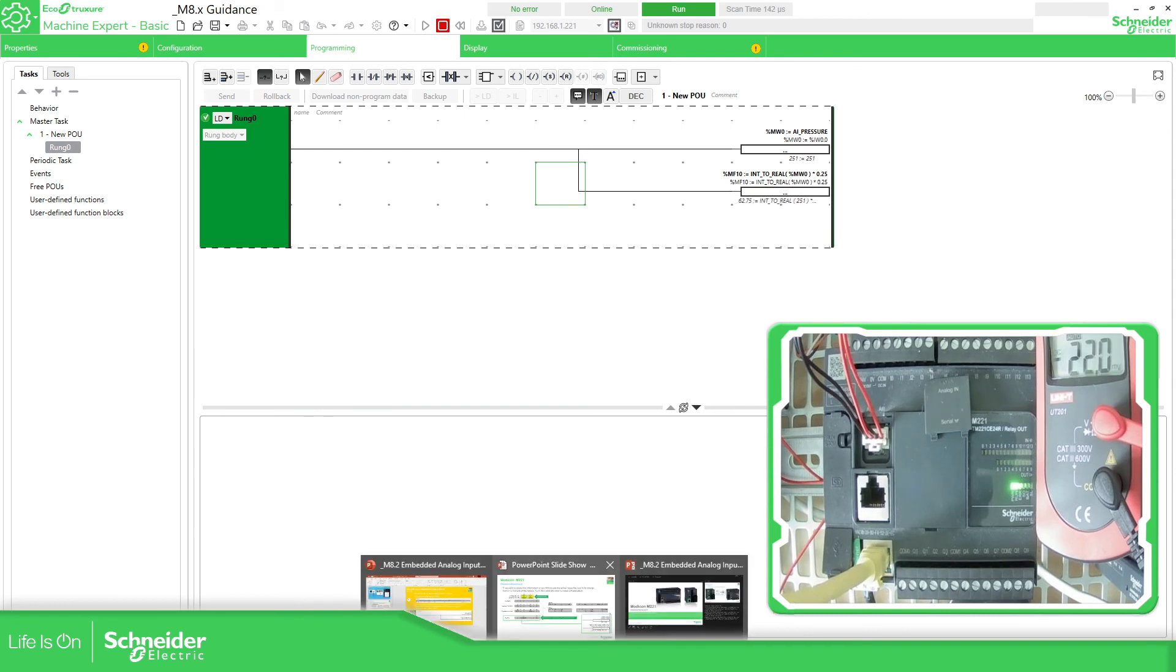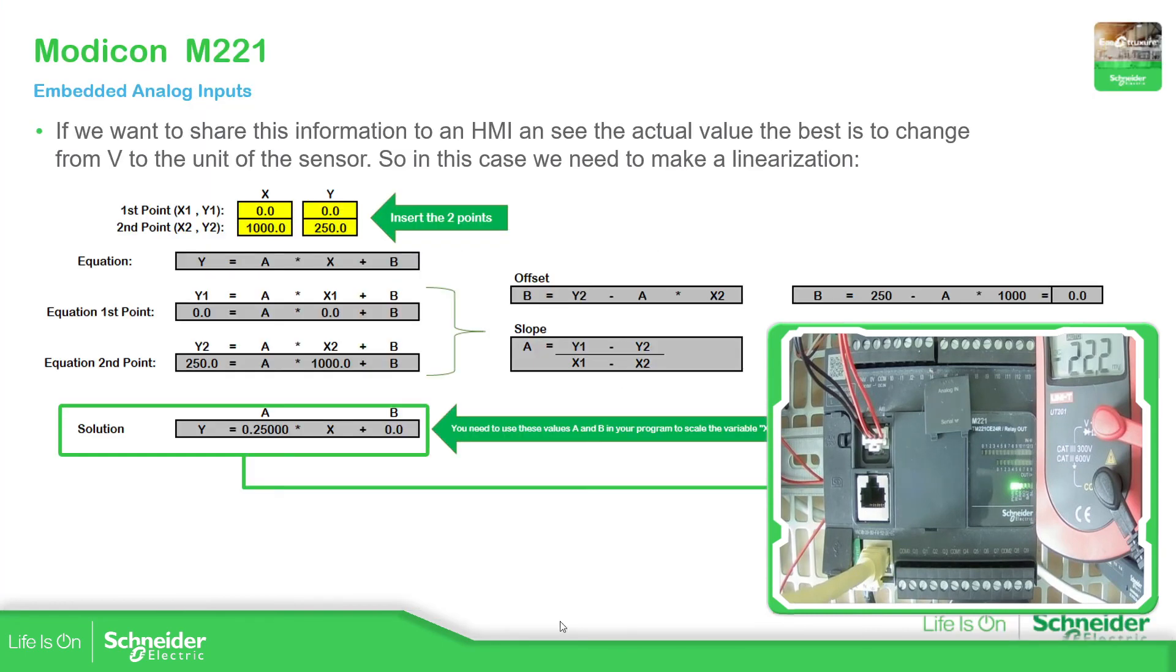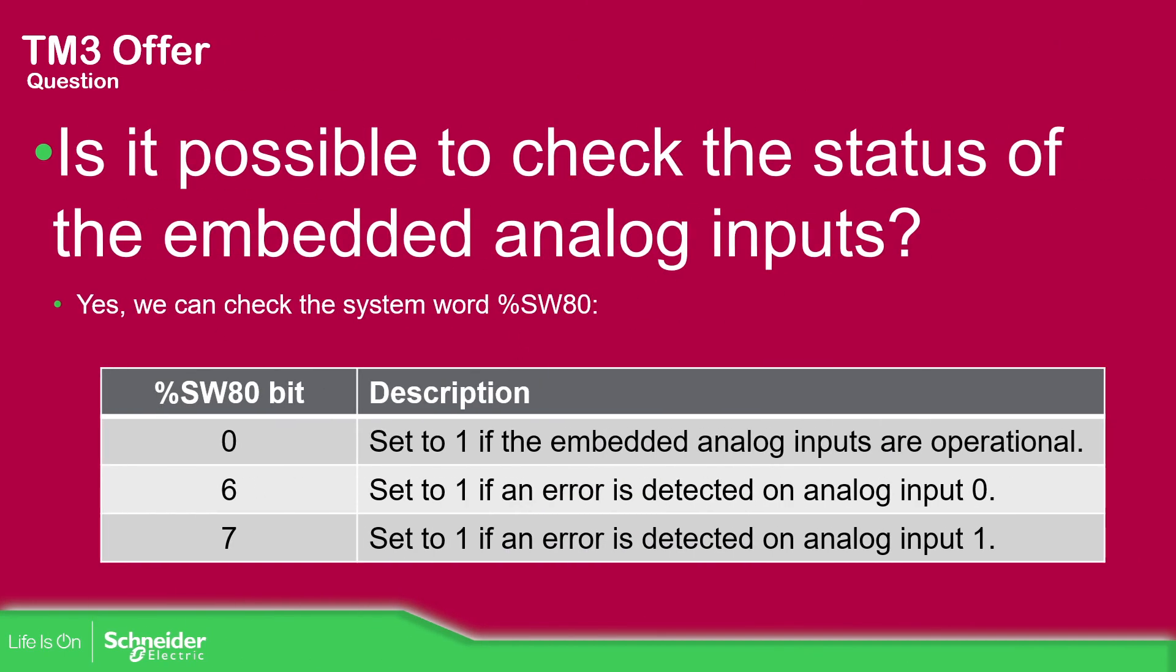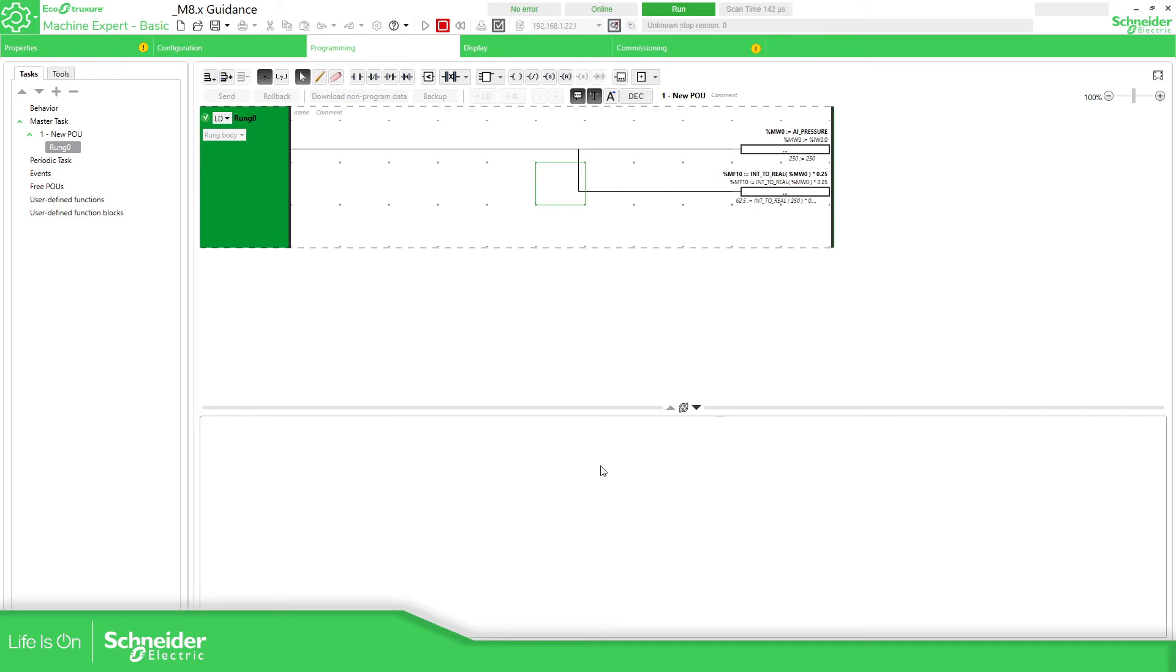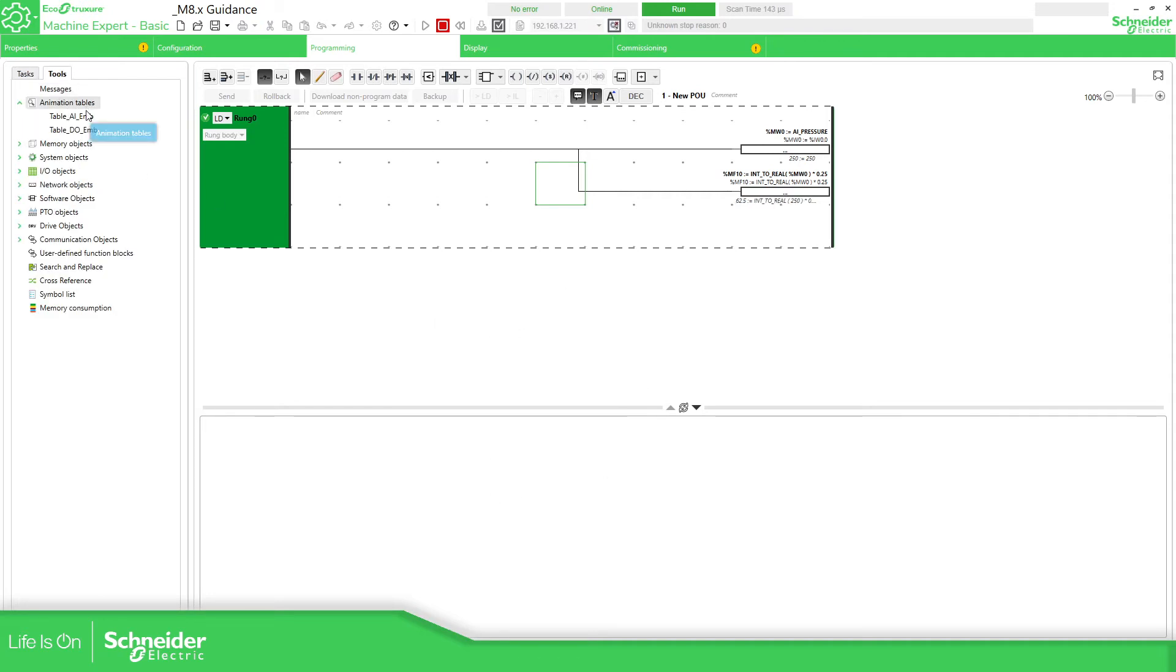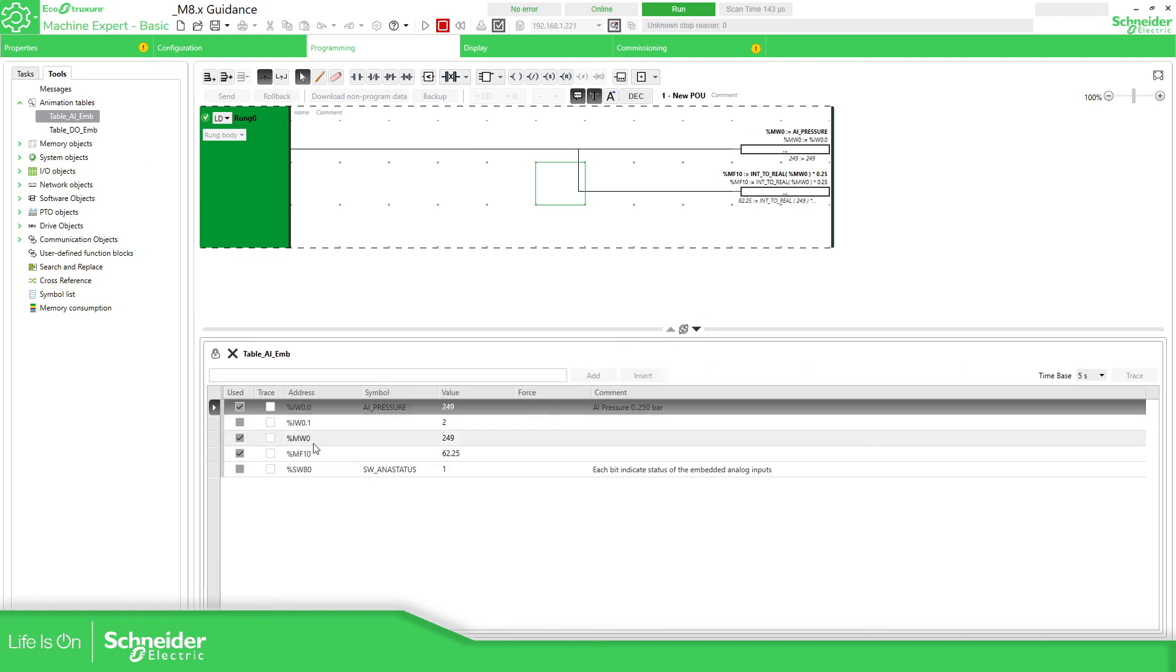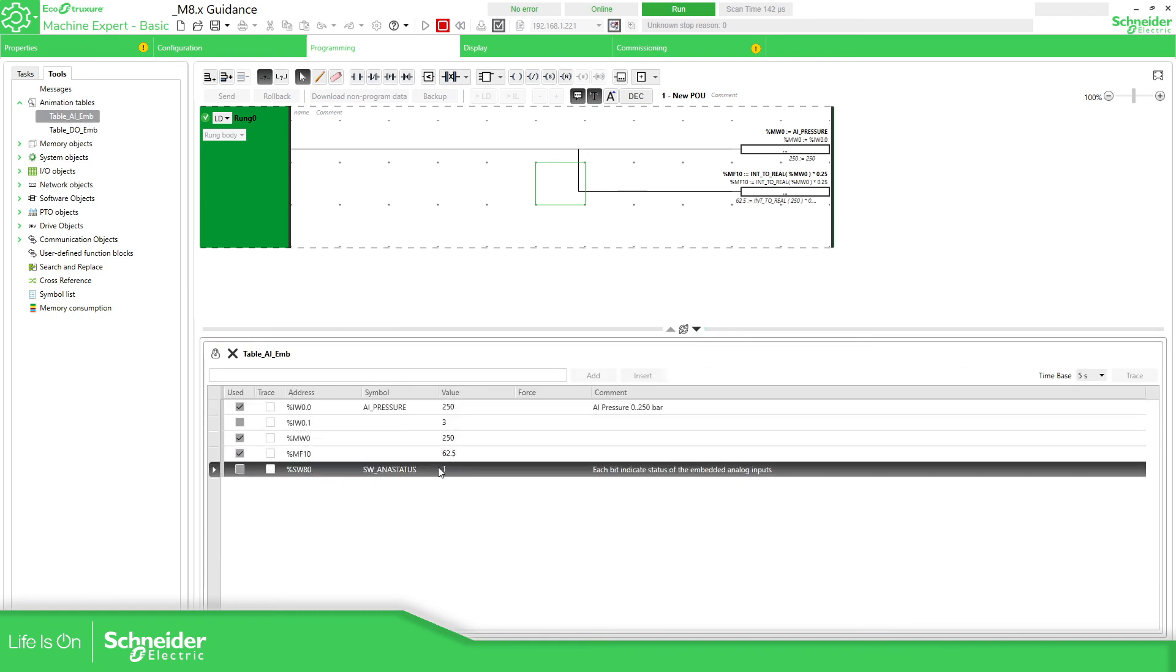If we continue with the presentation, we are also able to check if we have a problem on the analog input. That's why we have the %SW80. So if we go to the software now, we create an animation table. You can use the SW80 to see if everything is all right or not. And you can see here this value is in one so it means that everything is all right.